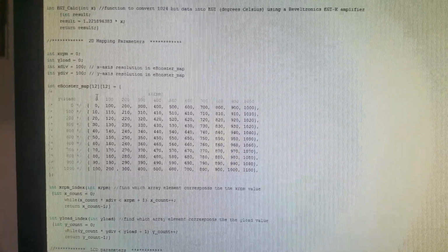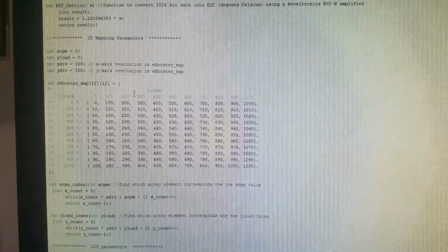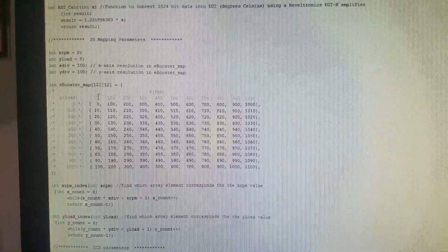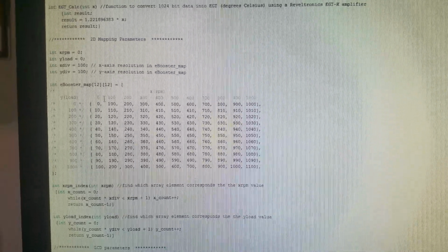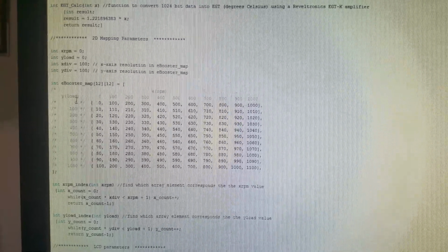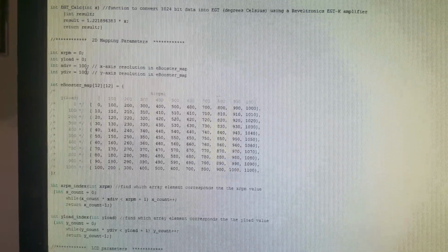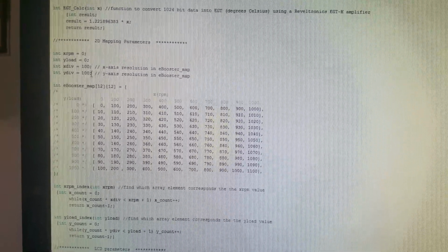And so I've defined essentially an x-axis, which right now I'm calling x-RPM, but this could be any input and any value. I just need to be sure I adjust the code to accommodate. And then same thing for the y-axis. And my intervals here, it's a 12 by 12 map. The step intervals are about 100 for each.